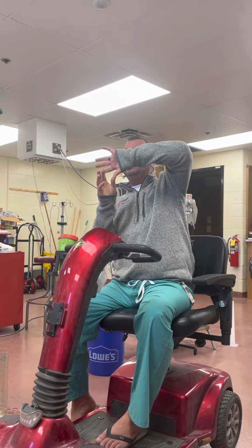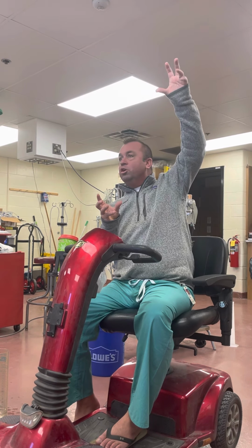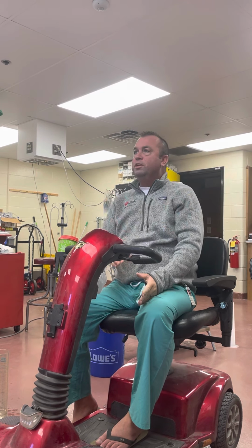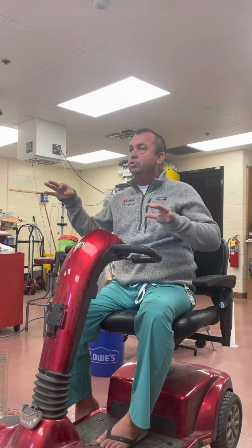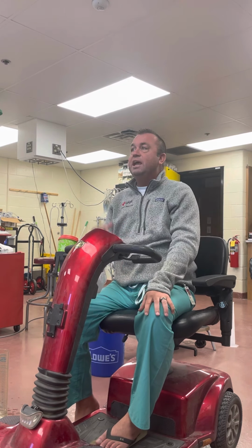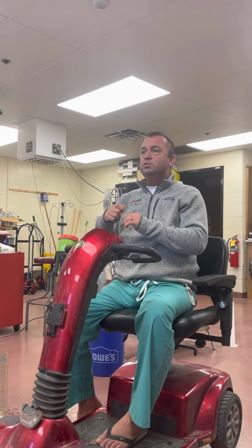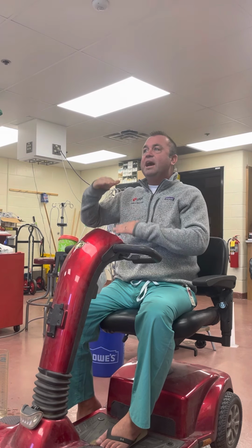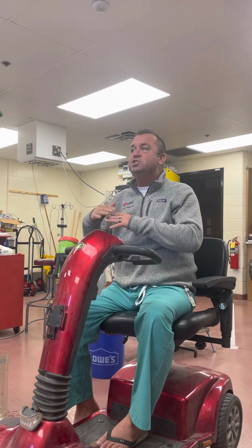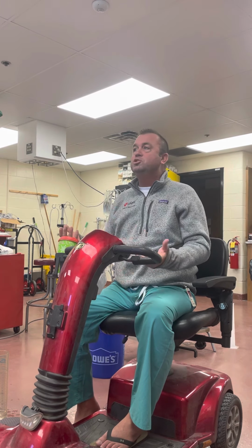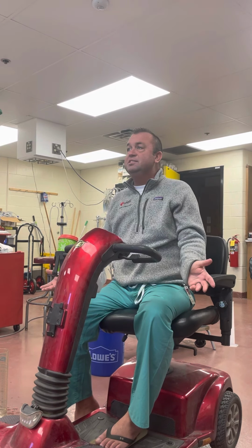Then we have to walk the air out, meaning we have to keep the air up in the tubing until we create a long enough part of that siphon where when we put it down, it chases the air out. We simulated this using a plumber's loop, a simple loop in tubing where we could inject a bolus of air, and then depending on the different size of tubing we were using, you got to investigate the height gradient of each individual piece of tubing and how much that height gradient was needed to push through a certain bolus of air. Obviously, a very small height gradient is needed to push 10 cc's of air out.